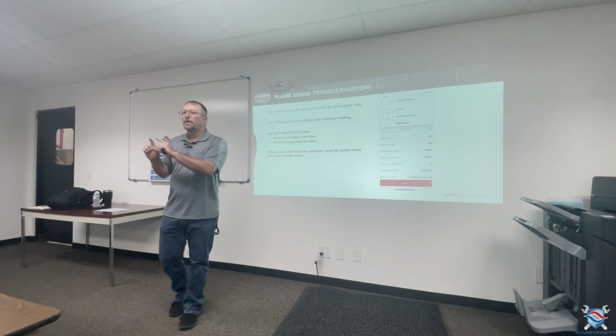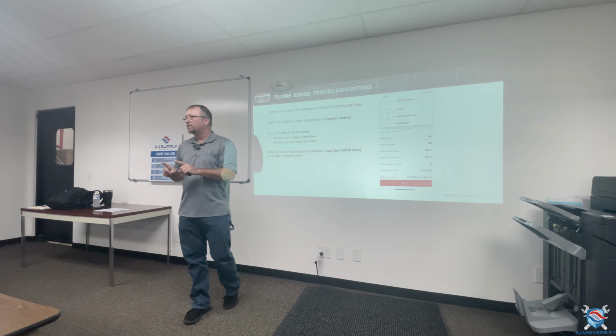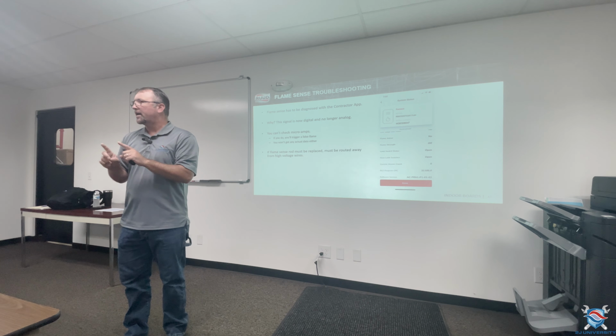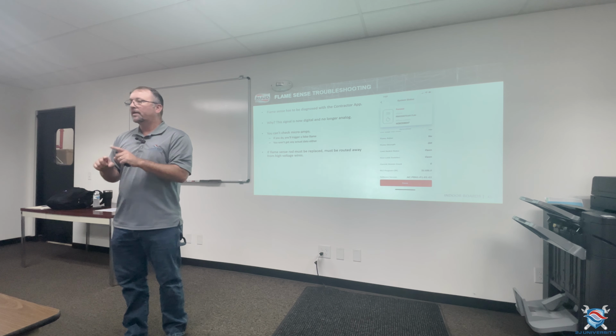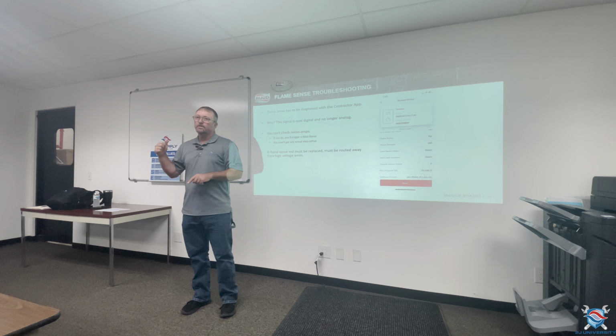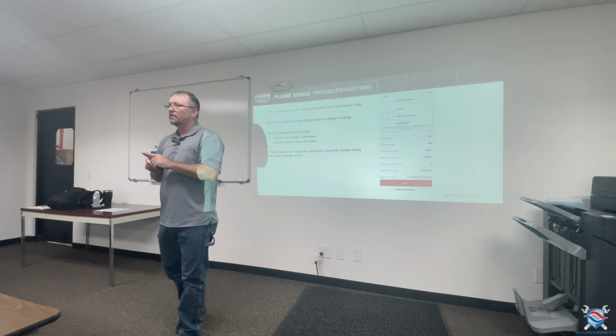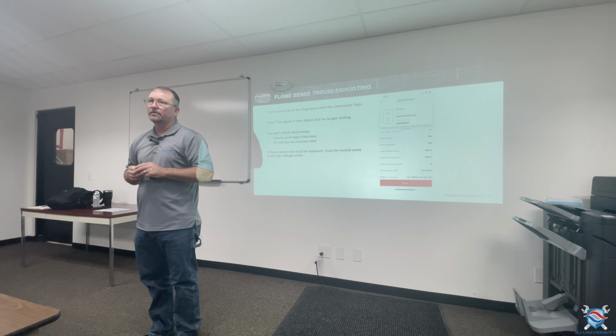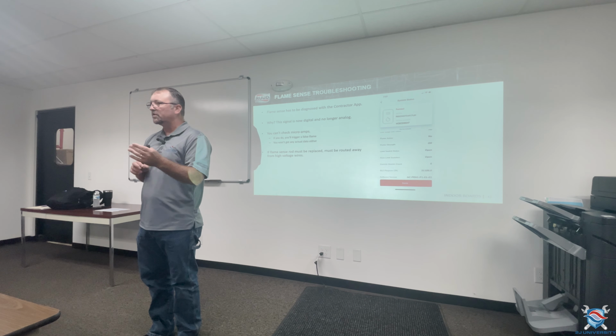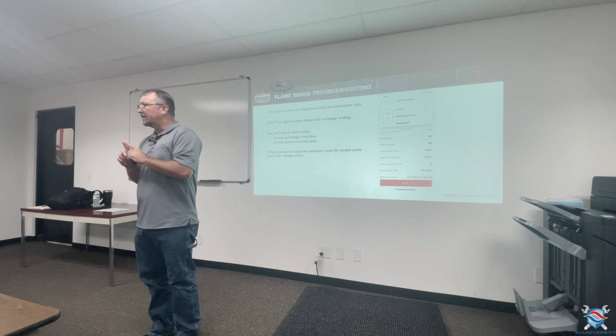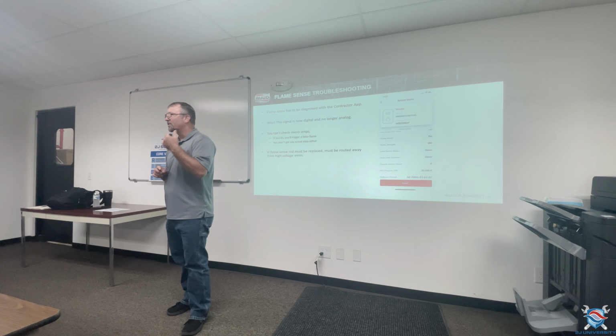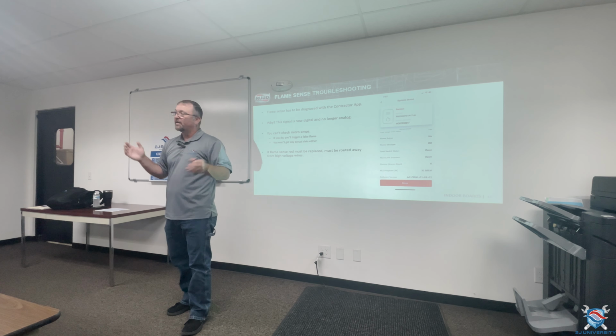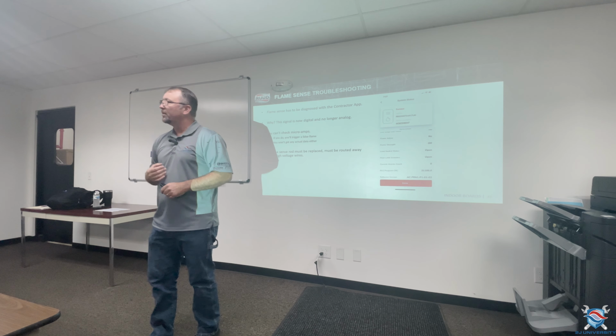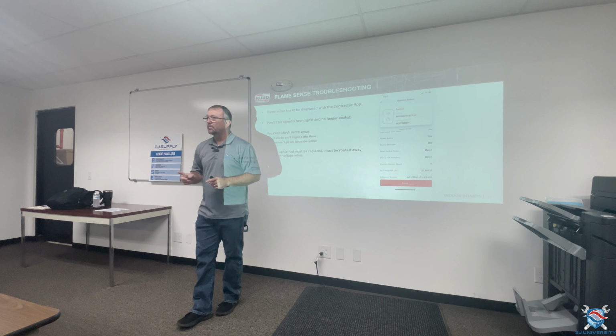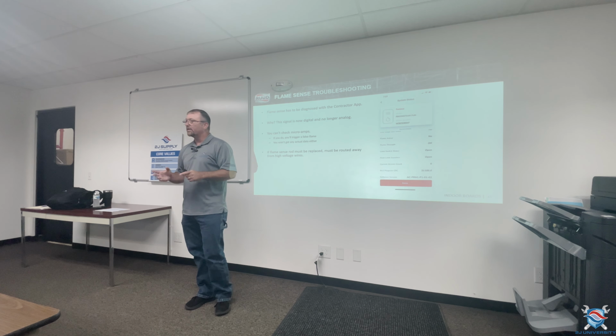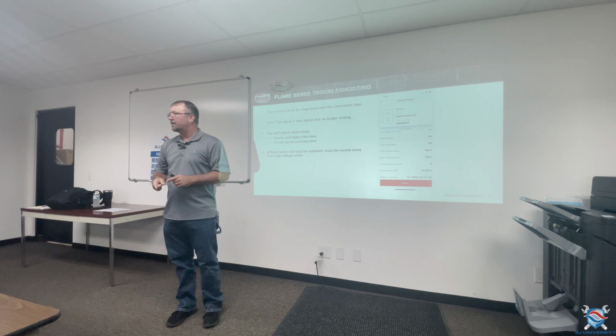I've had units that guys have gone out and replaced 4 boards and still have that same issue. And something that they're testing in the factory right now is separating those wires. What I can tell you, and I just took a phone call before I walked in here, is a guy replaced a board, left them together, because I've been working with this same contractor on this issue. He kept them together to see if it truly was the board or if separating the wires was working. He didn't separate the wires, and guess what? 5 days later, he's getting a phone call. Hey, my alarm's going off on my Econet again. I'm getting that same code. And he just called me to let me know, hey, I'm going to separate the wires because that seems to be the fix. So if you guys install one of these, just make sure you reroute that.